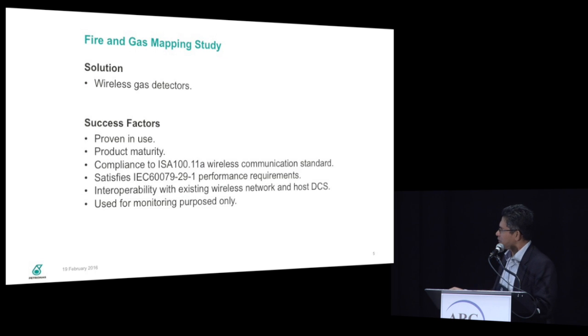Looking back at the challenges, as I mentioned, we had the options of wired or wireless. If we were to install wired, the challenges are the scarcity of spare junction boxes at site, and the high risk involved when laying new cables for detectors, especially excavation. Installation and commissioning of new detectors have to be done online while the plant is running. And of course, the remote location, the crossing, the bund walls, everything will consume a lot of cost for the wired cable installation.